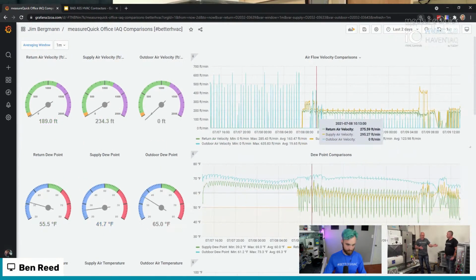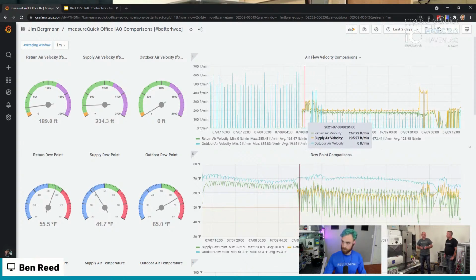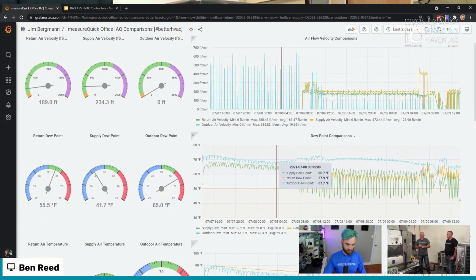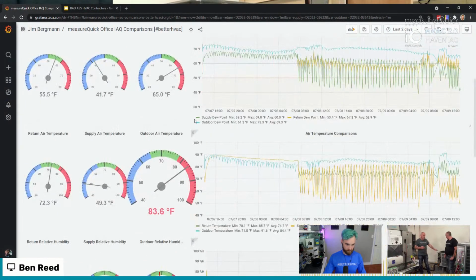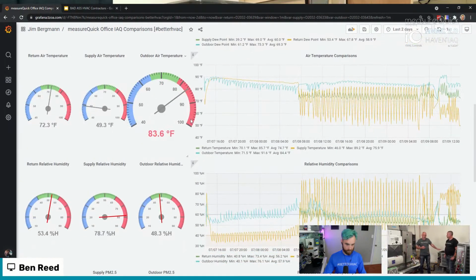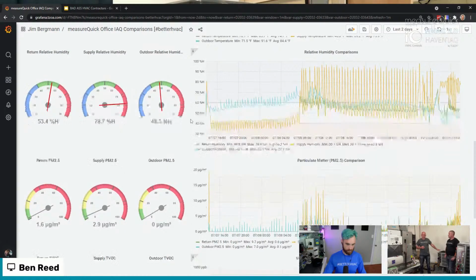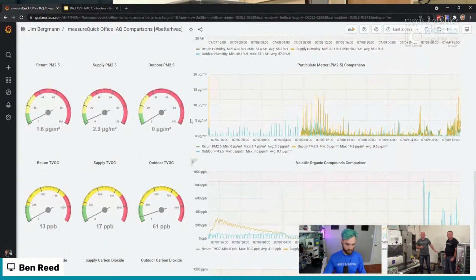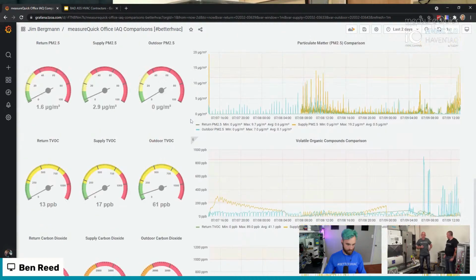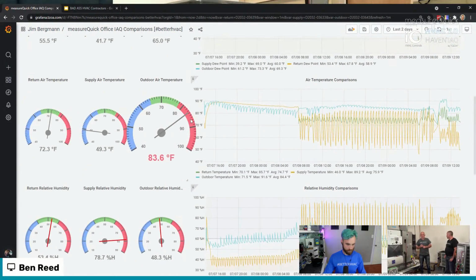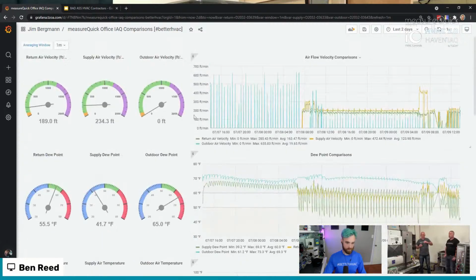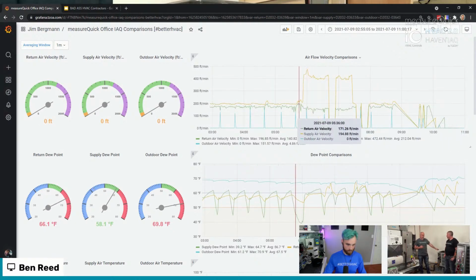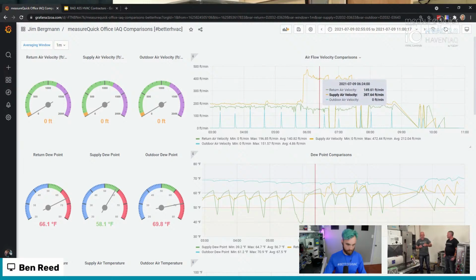So Nate sat down today, we went through and programmed the thermostat and got all that tied in. Then we can do a couple of different things—number one is multiple stages. These Bosch units are incredible if you set them up properly; if you don't, they don't work so good. The trick with this unit is you need a 2-stage thermostat, so we get cycles that go to the second stage, then ramp back to first stage, then up to second stage again, ramp back to first. Because the inverter system doesn't respond right away, this allows us to get that cold coil to wring water out of the system.